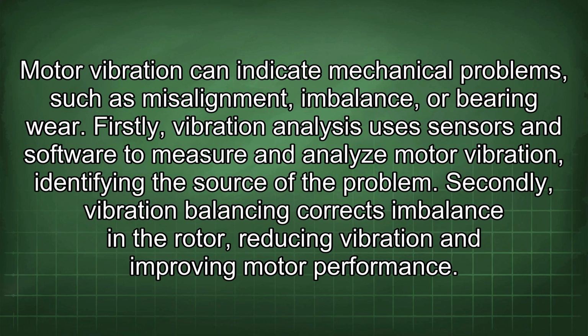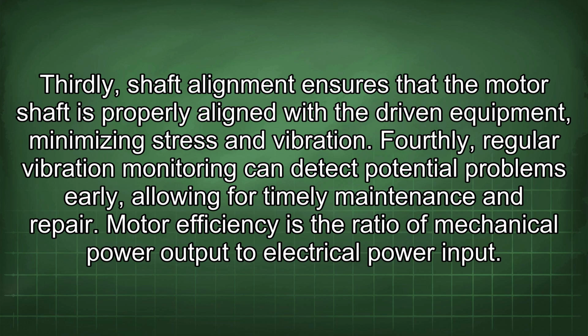Motor vibration can indicate mechanical problems such as misalignment, imbalance, or bearing wear. Firstly, vibration analysis uses sensors and software to measure and analyze motor vibration, identifying the source of the problem. Secondly, vibration balancing corrects imbalance in the rotor, reducing vibration and improving motor performance. Thirdly, shaft alignment ensures that the motor shaft is properly aligned with the driven equipment, minimizing stress and vibration. Fourthly, regular vibration monitoring can detect potential problems early, allowing for timely maintenance and repair.